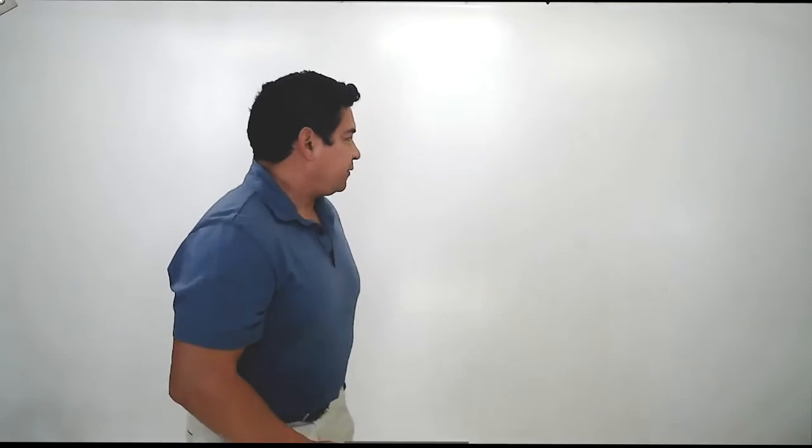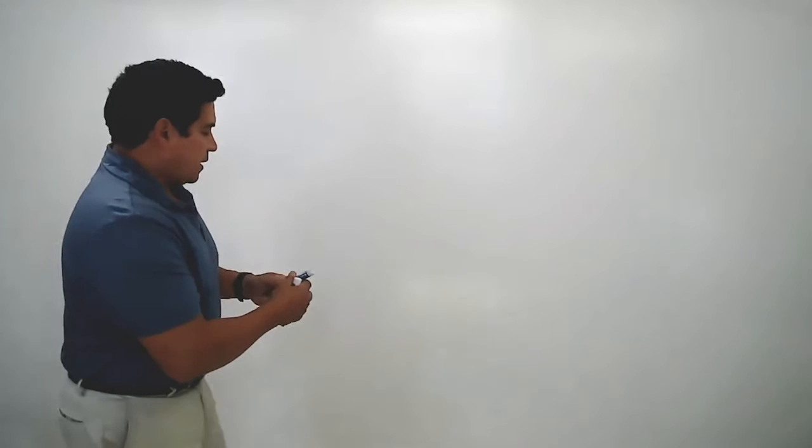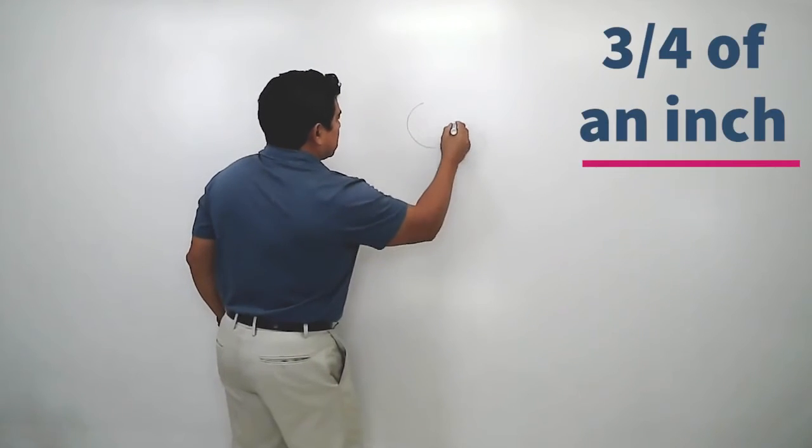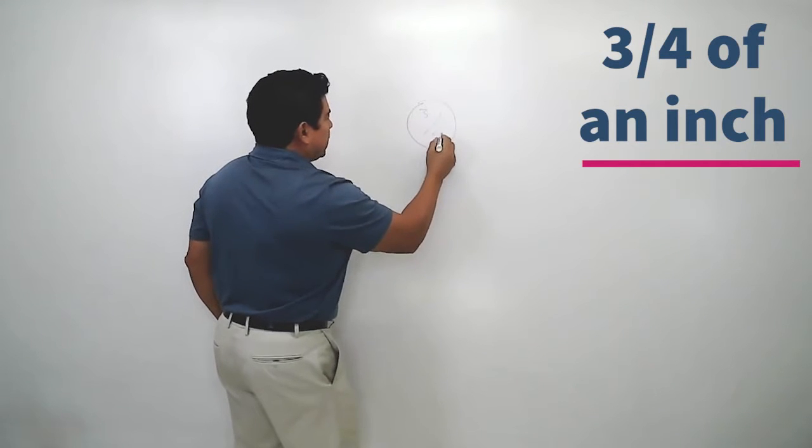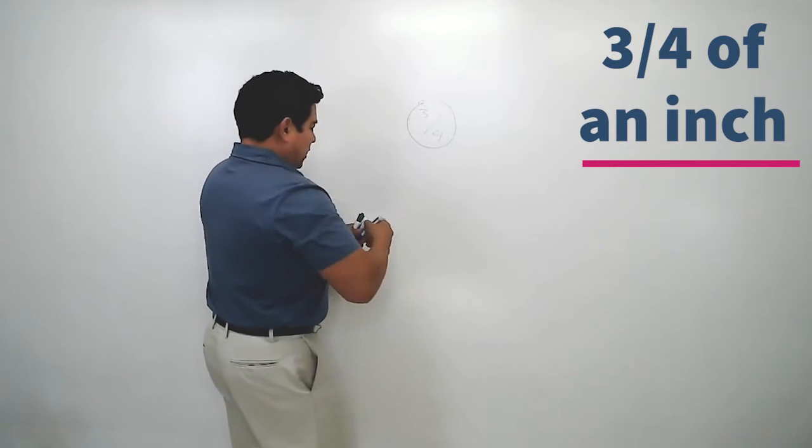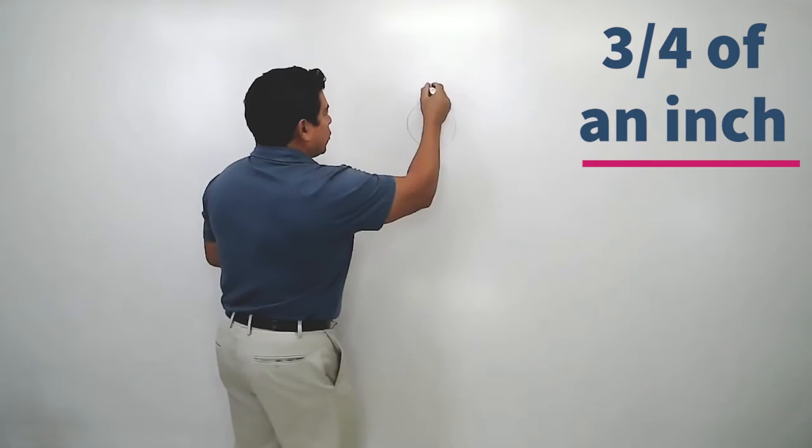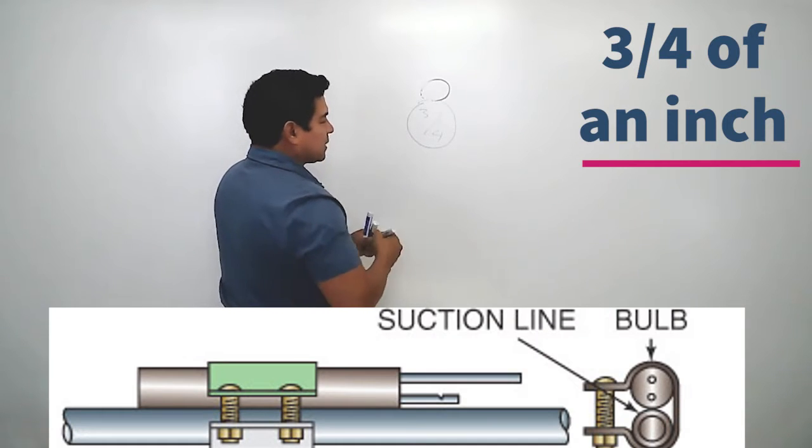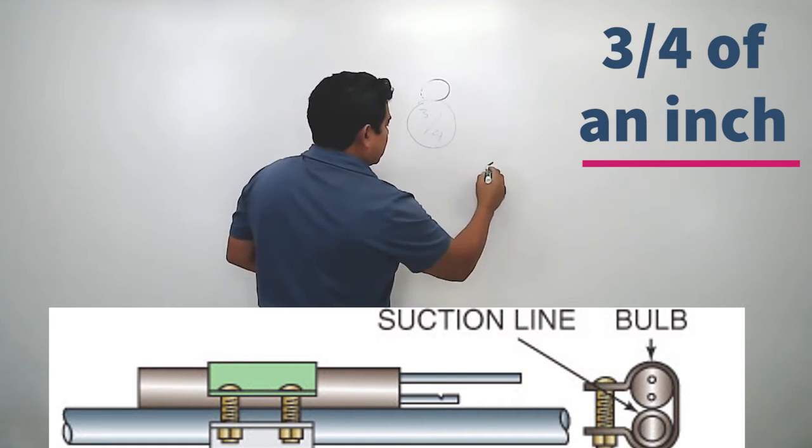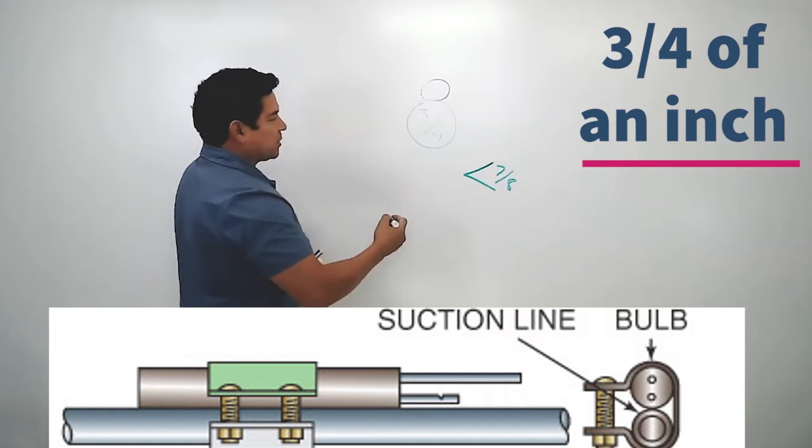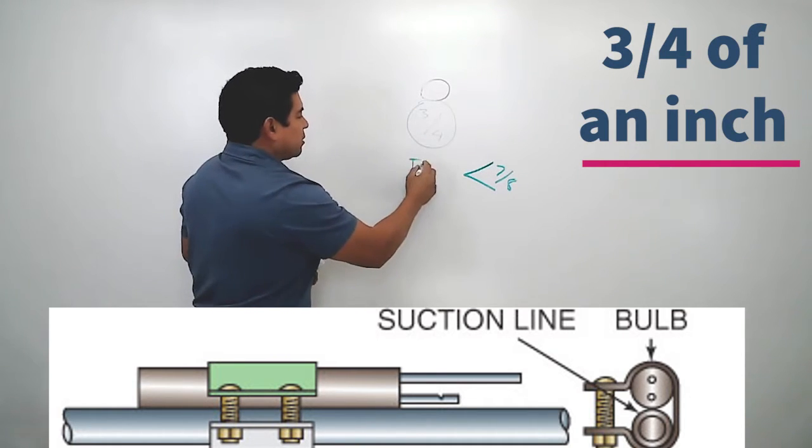One is that if we have a suction line that happens to be, let's say, three quarters of an inch, then the sensing bulb is going to have to be up on top. Rule of thumb says that if the line is smaller than seven eighths, then it needs to be on top.